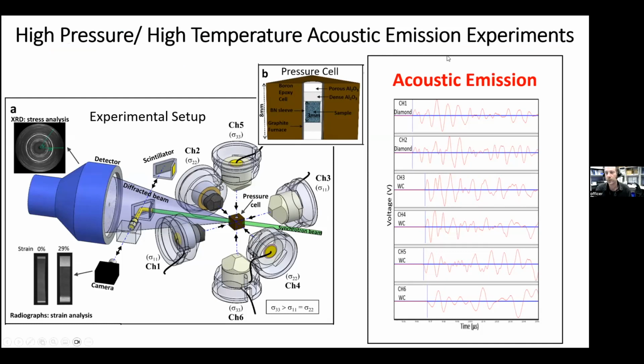And the anvils will then compress the pressure cell to bring it up to high pressure and bring the sample up to high pressure. But a key point, this is in the D-DIA apparatus, where the top and bottom anvils can move independently from the surrounding. So once you're under pressure, you could advance these 2 anvils and deform the sample. We also have a synchrotron beam. So you have a monochromatic beam in which you can collect radiographs and X-ray diffraction patterns, which I'll talk about in a second, to measure stress and strain.